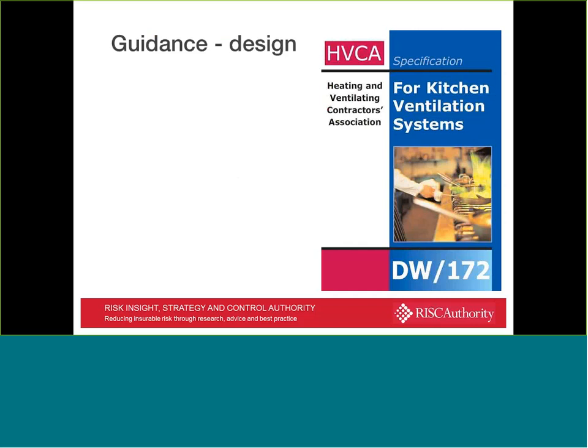So, in terms of design, where do we go? Well, the HVCA, or now as they call themselves, the Building and Engineering Services Association, produce this particular document, DW172, which is a specification for kitchen ventilation systems, and provides some excellent guidance in there as to how systems should be effectively designed to ensure that they fulfill their function in providing a degree of fire protection, exhausting air, and providing adequate working conditions, but with a particular focus in this instance on the kitchen systems that we're dealing with. This document is called upon in other guidance in lots of other locations, including our own RC44 document. So it's very much seen as an industry bible.